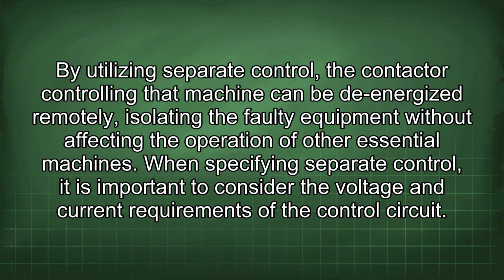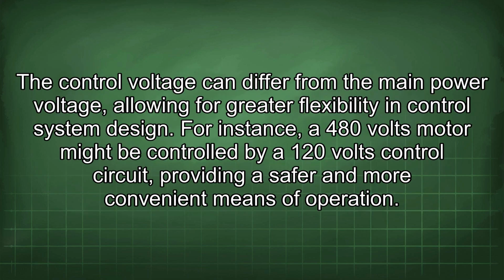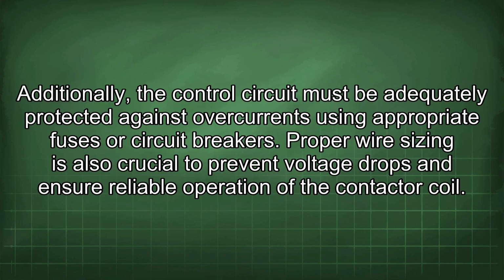When specifying separate control, it is important to consider the voltage and current requirements of the control circuit. The control voltage can differ from the main power voltage, allowing for greater flexibility in control system design. For instance, a 480 volt motor might be controlled by a 120 volt control circuit, providing a safer and more convenient means of operation. Additionally, the control circuit must be adequately protected against overcurrents using appropriate fuses or circuit breakers.